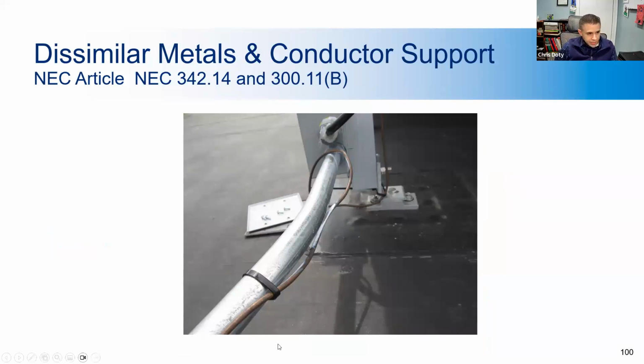Here you have another example of the same thing. You have a raceway that's being used to support a conductor, which is against code. The only time you can do that really is for like data wires. And also you see the galvanic corrosion again between the copper conductor and the coating on the raceway. So again, this will corrode until there's basically nothing left. And it'll probably corrode in a lot of places because it's supporting this copper wire. So it's going to eventually deteriorate, and then you're going to have no ground connection again.